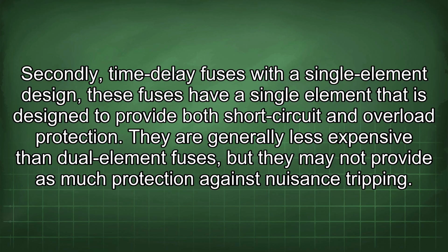These fuses have a single element that is designed to provide both short circuit and overload protection. They are generally less expensive than dual-element fuses, but they may not provide as much protection against nuisance tripping.